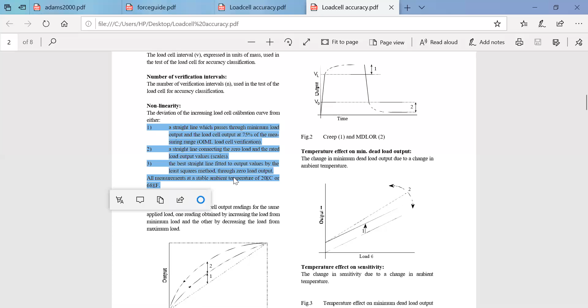Then the other nature of the load cell is hysteresis. We spoke about what we mean by hysteresis and the types of hysteresis loop in our previous modules. Here you can see the difference between the load cell output readings for the same applied load. You will have different load cell output readings depending upon the loads or slotted weights you apply on the instrument, right? One reading is obtained by increasing the load from the minimum load, and the other by decreasing the load from the maximum. We have even shown you how to perform a load cell experiment, one from maximum weight to the least, another from the least to the maximum. Based on this trend, you plot the load versus the output reading you get, and we trace it to understand the nature of the hysteresis here.